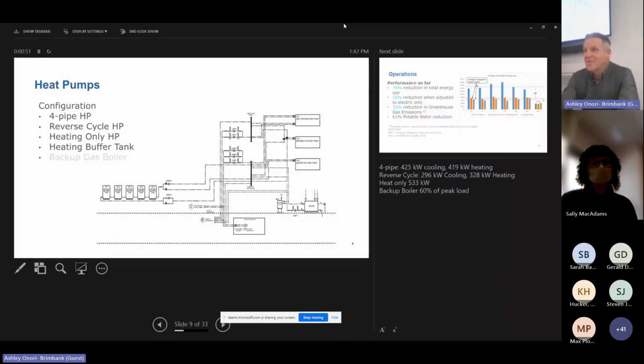We do have a number of buffer tanks that are well intended to use when a heat pump goes into defrost cycle, for example. And we do have - and I've grayed this out a little bit - a gas backup boiler that's supposed to only kick in for emergencies. I have to say that at the moment it still kicks in every now and then, and we know that's an issue we need to work on, but it's essentially tuning. The heat pumps themselves should be able to cover most of the heat demand.